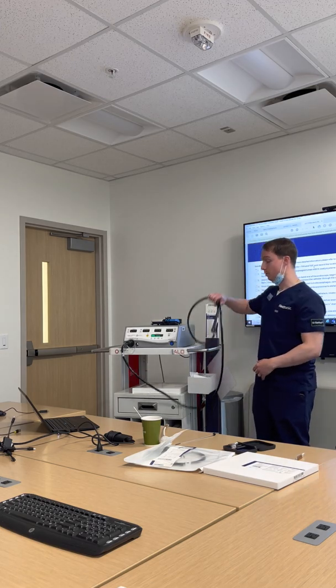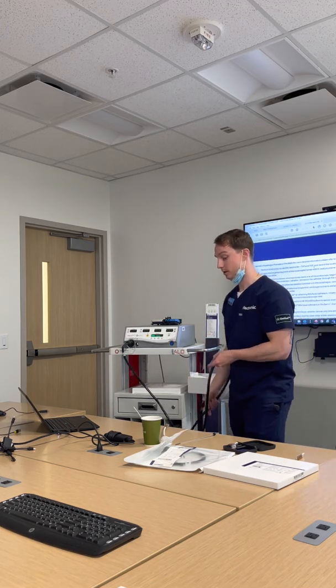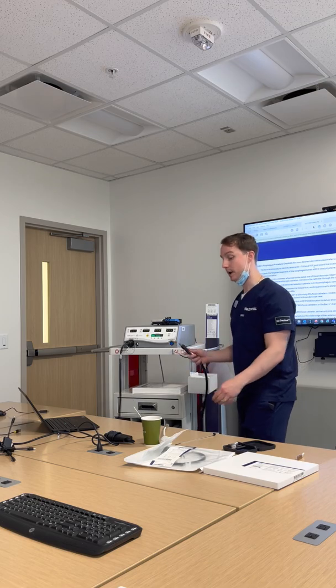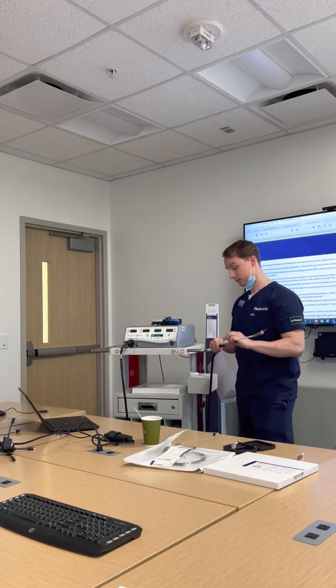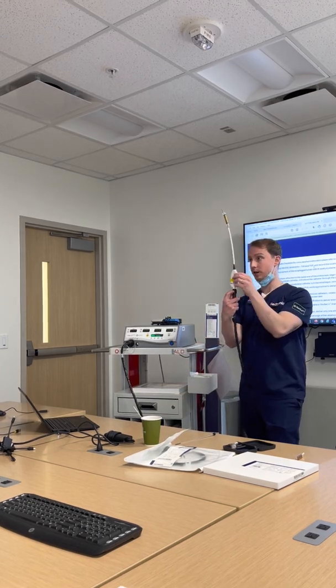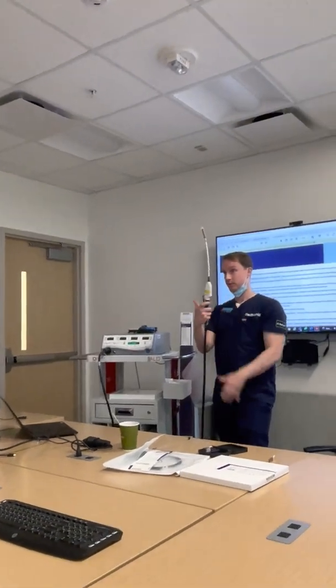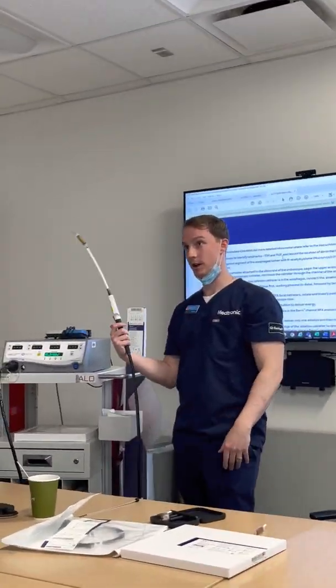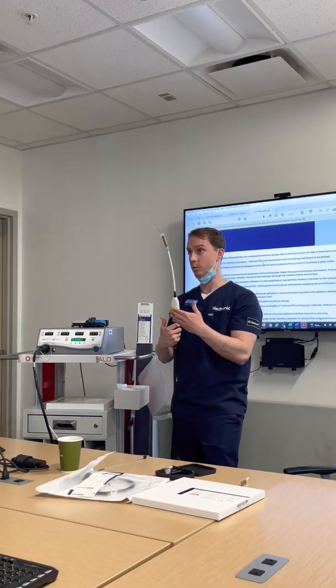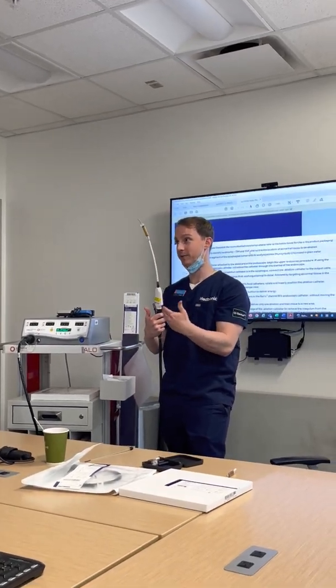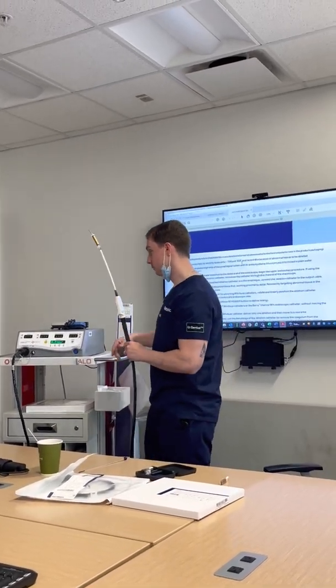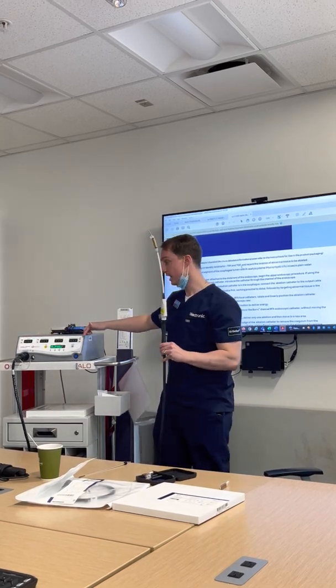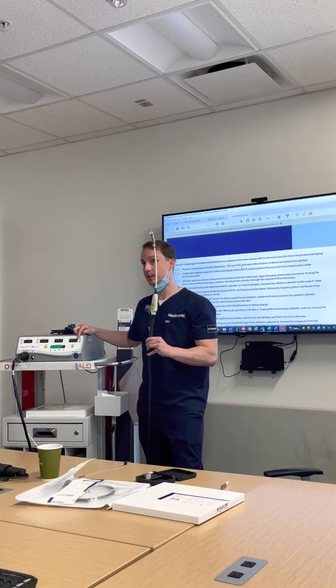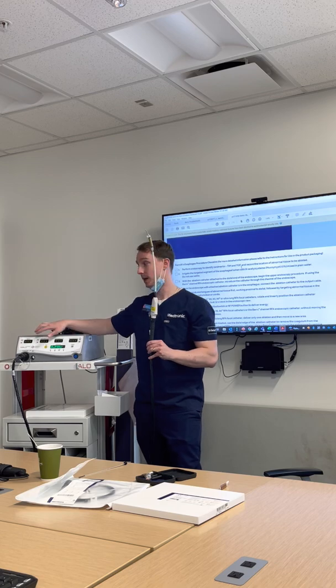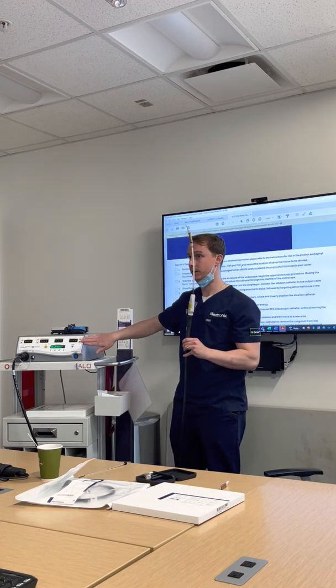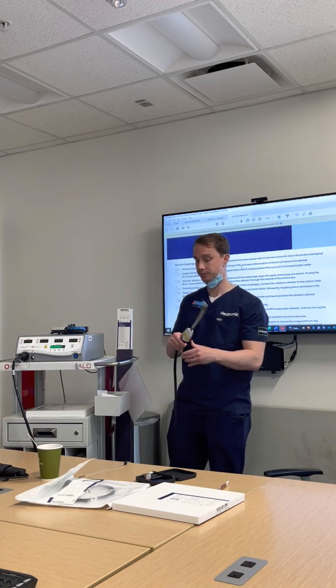Once we connect it to the system, this one is my demo handle, so it's going to give us some errors. There's a little dot, again a collar here, it clicks on. It's not going to give you that error because this says, what is this catheter, this is not the right catheter, why did you connect this? But once we connect the catheter, all of these preset settings that we talked about will pre-populate. Again, please do not touch any of these. They are pre-populated per catheter.